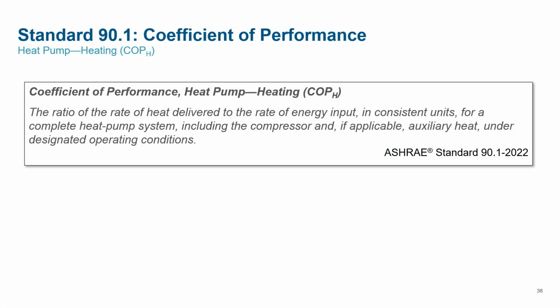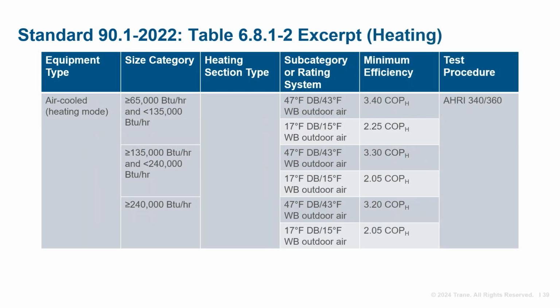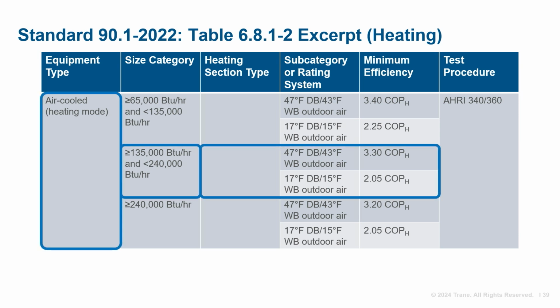Heat pump units also have separate heating mode efficiency requirements. To express this, 90.1 uses coefficient of performance heat pump heating, or COPH. This metric is defined as the ratio of heat delivered divided by the rate of energy input in the same units. It's important to note that this does include auxiliary heat if that's being used at specific test conditions. For heating, we have 2 ambient temperature-based requirements. For our example heat pump, the COPH must be at least 3.30 at an ambient temperature of 47 degrees Fahrenheit and 2.05 COPH at 17 degrees. Ray is going to discuss some of these common terms next.